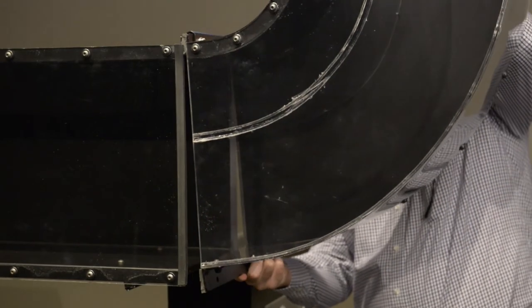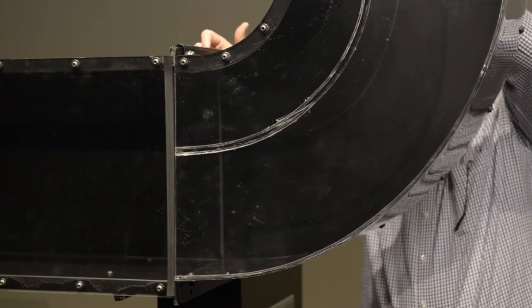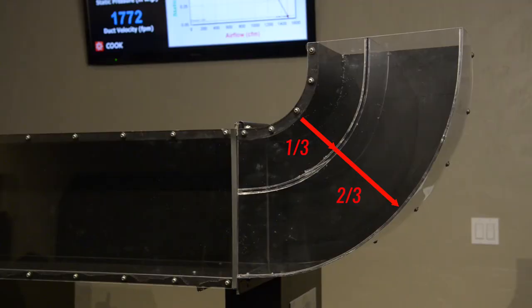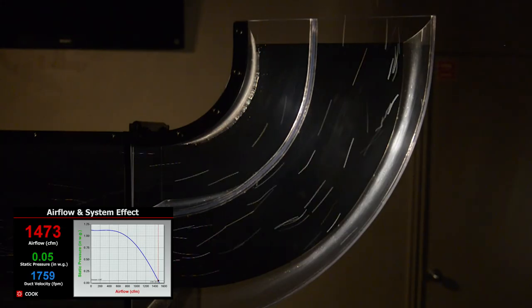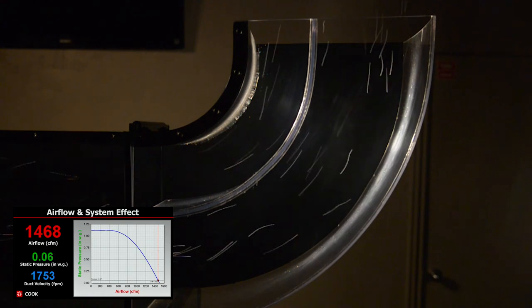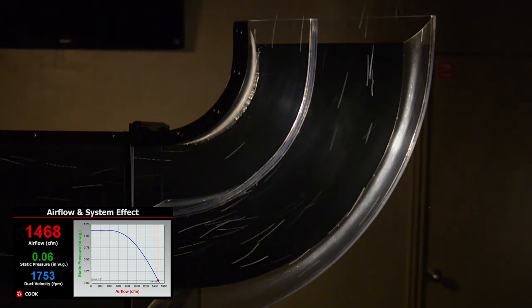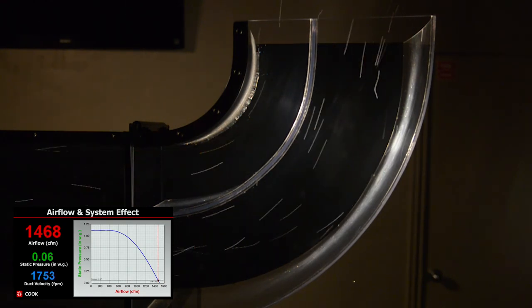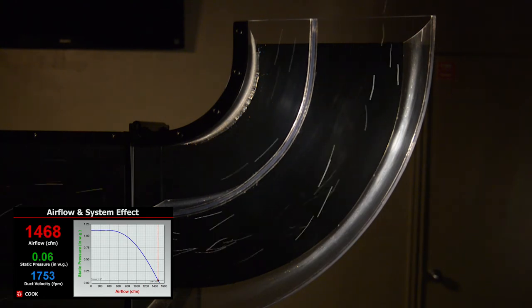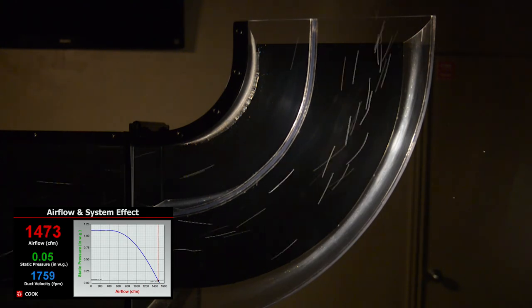Take a short radius elbow and put a splitter at a third the width of the duct from the throat. Looking closely at the geometry, we now essentially have 2 long radius elbows. The performance is nearly as good as the large radius elbow, taking up much less space. Having thoroughly explored elbow fittings, let's take a look at what are commonly known as T fittings.